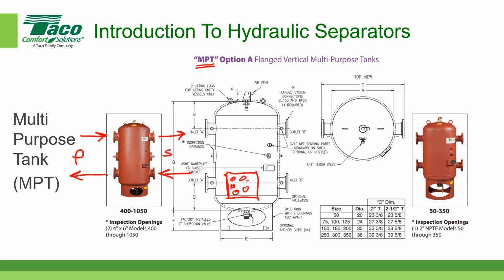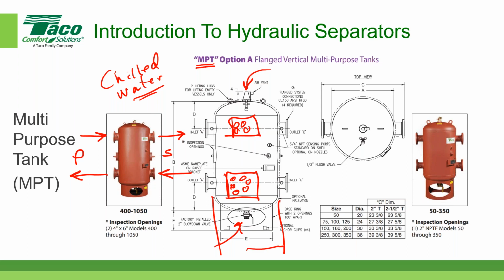I'll make a bunch of Pall rings inside a basket. And you can get it to operate as an air vent. There's an air vent as an air separator, a dirt separator, and a hydraulic separator. So multi-purpose tanks have, as the name implies, multi-functionality. Now, one of the things I want to caution against is that with multi-purpose tanks, when it comes to chilled water, you have to look very carefully at the configuration for a chilled water system, because if the diameter of the tank is too great, you may get some premature mixing that you don't want to happen.